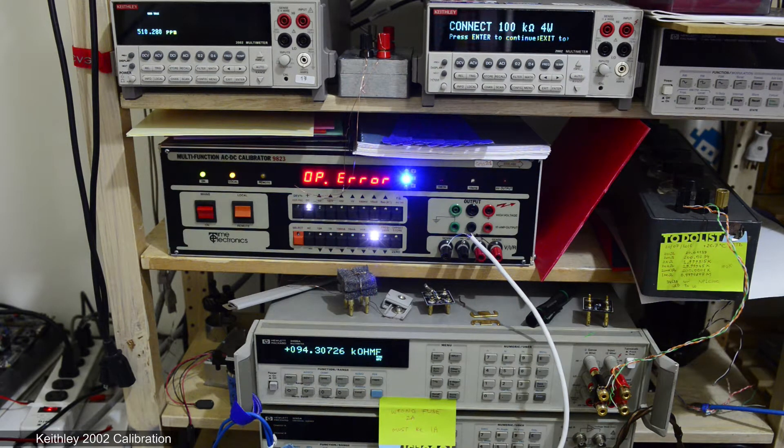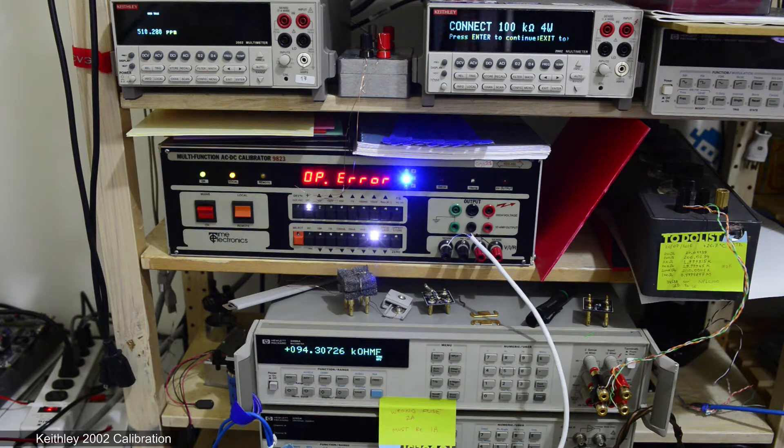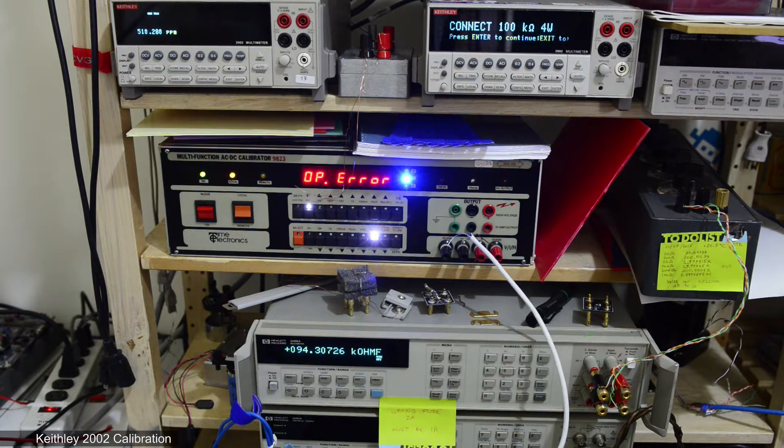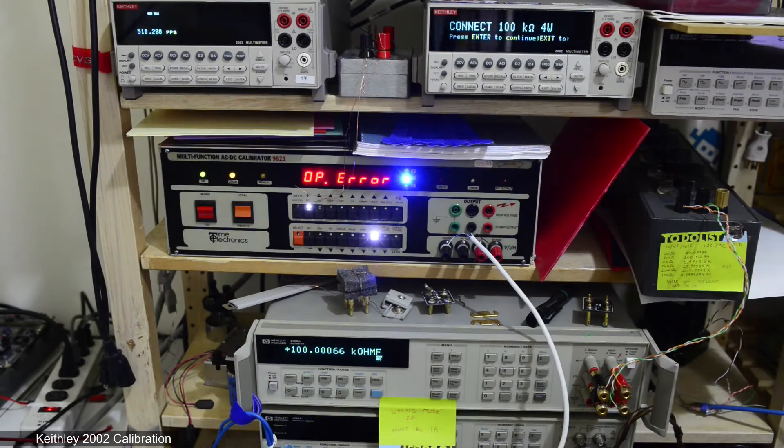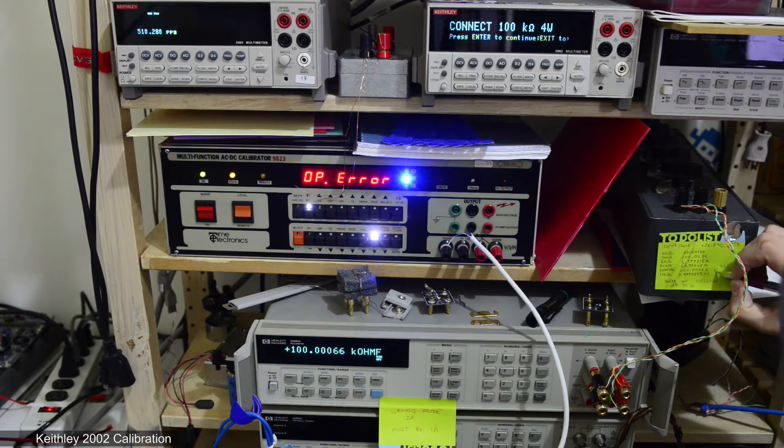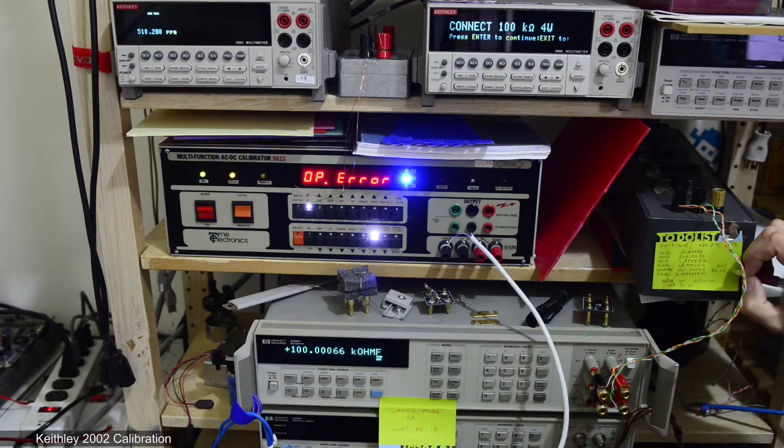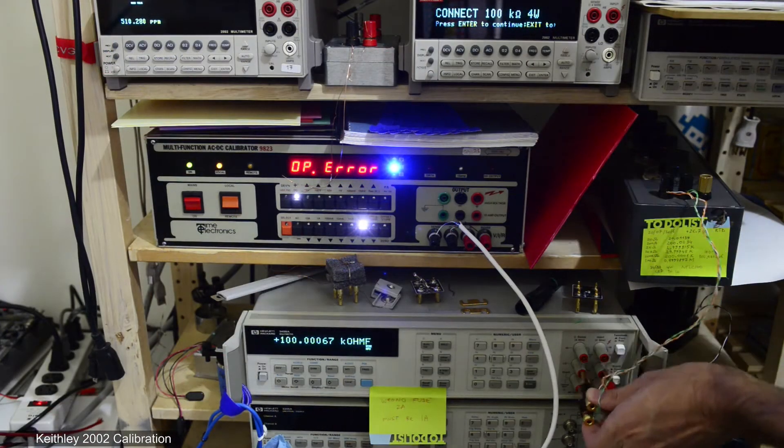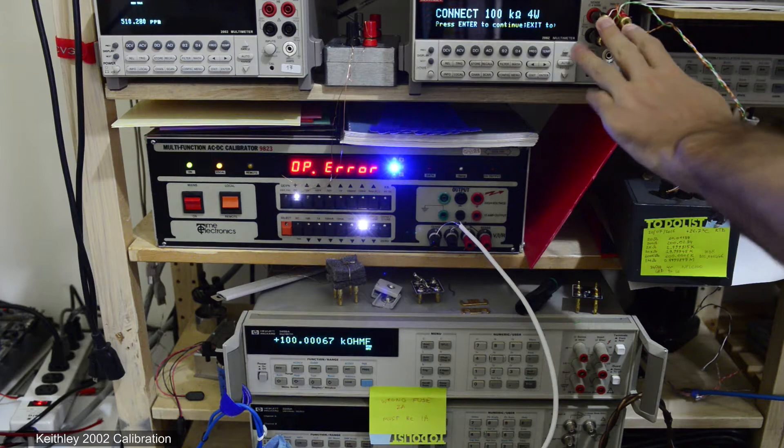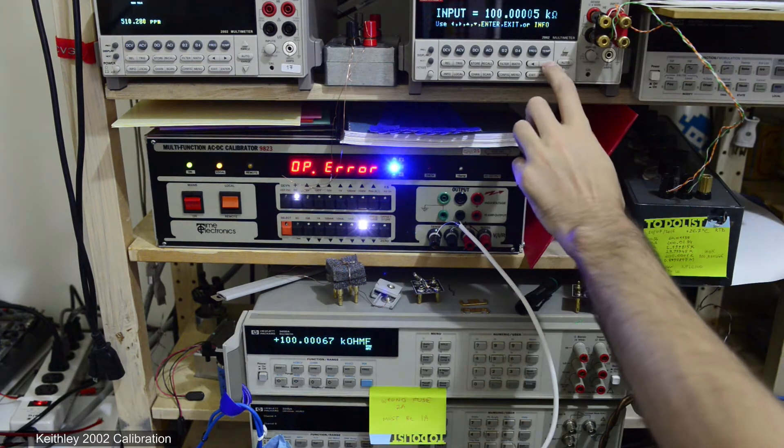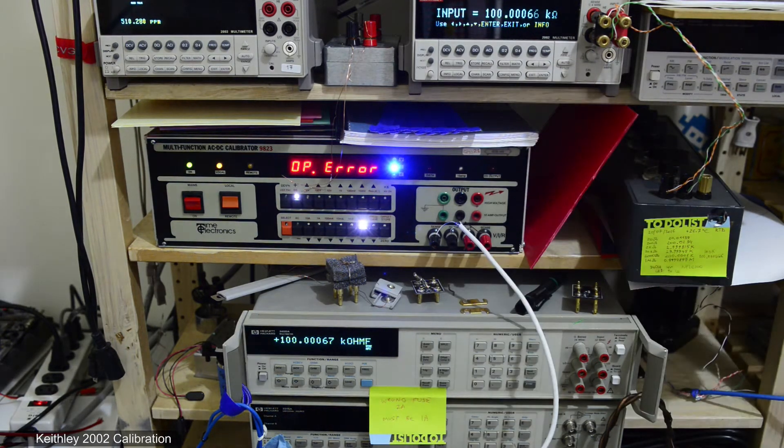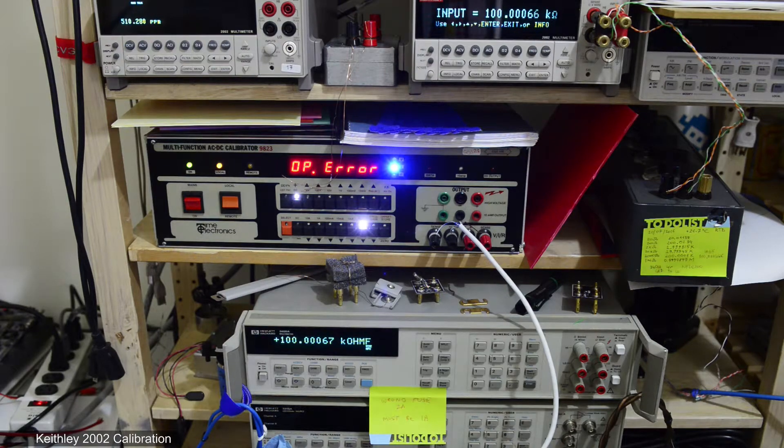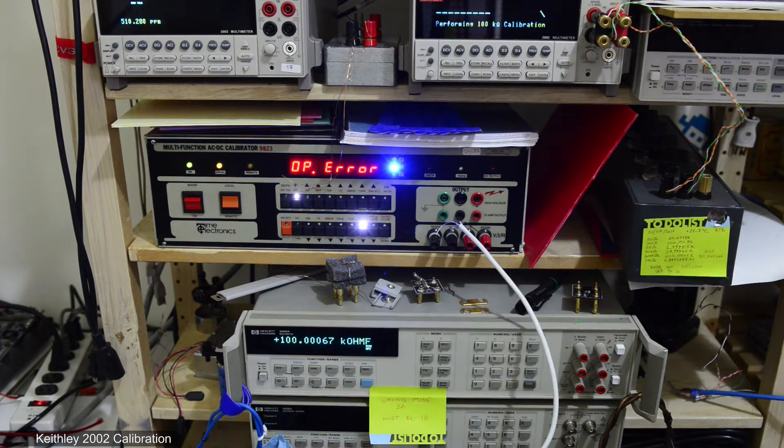HP 3458A will be used as a transfer standard and the source will be a multifunction AC-DC calibrator from Time Electronics model 9823. As a resistance standard I'll use an ACI resistance decade model DB52.